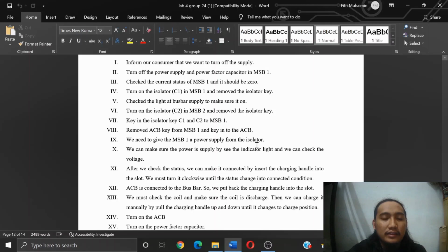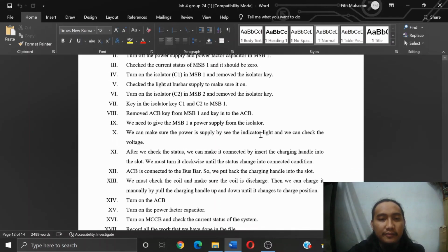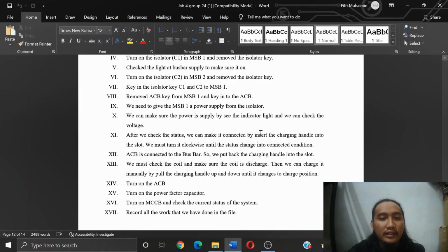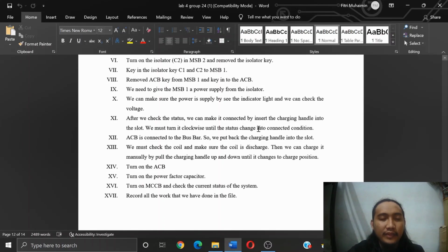Then turn on the isolator C1 in MSB1 and remove the isolator key. Then check the light at the busbar supply to make sure it is on. So then turn on the isolator C2 in MSB2 and remove the isolator key. Next, we key in the isolator keys C1 and C2 to MSB1. Then we remove the ACB key from MSB1 and key it in to the ACB.